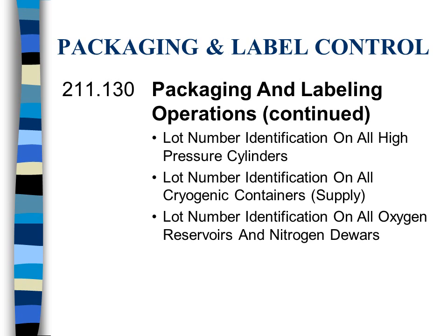Lot numbers are also required to identify medical gas products in the event of a recall. We can go back through history, through our production records, and through our delivery tickets and find out who received any of the affected cylinders and issue a recall to recover those cylinders.